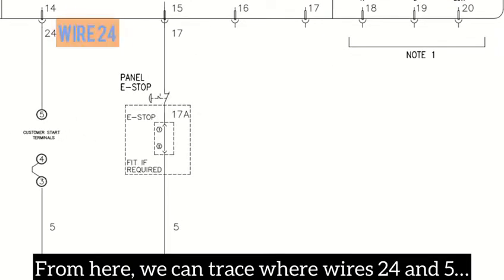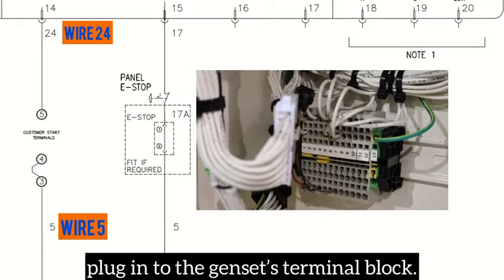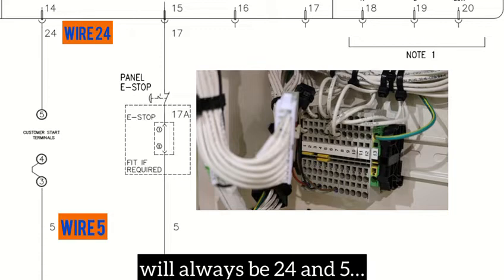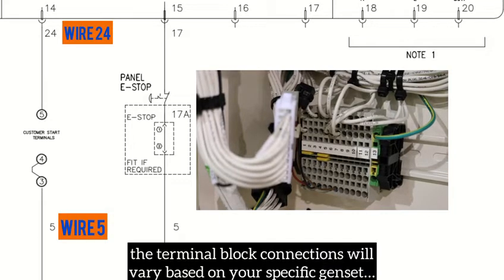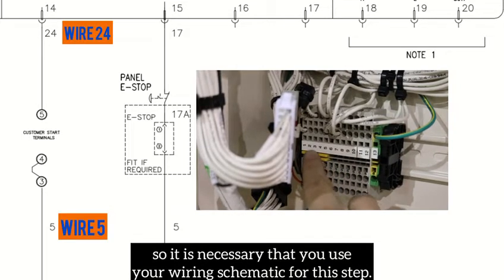From here, we can trace where wires 24 and 5 plug into the genset's terminal block. Please note that although the two remote start connection wires will always be 24 and 5, the terminal block connections will vary based on your specific genset, so it is necessary that you use your wiring schematic for this step.